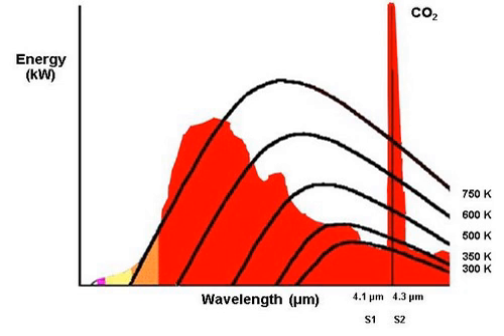Emission of radiation. A fire emits radiation, which the human eye experiences as the visible yellow-red flames and heat. In fact, during a fire, relatively little UV energy and visible light energy is emitted, as compared to the emission of infrared radiation. A non-hydrocarbon fire, for example one from hydrogen, does not show a CO2 peak at 4.3 micrometers because during the burning of hydrogen no CO2 is released.